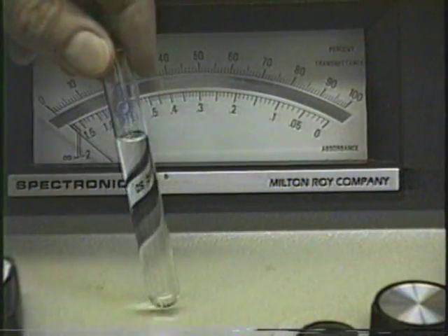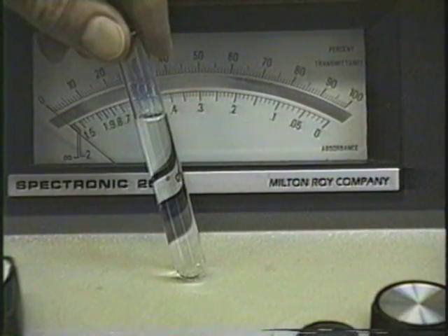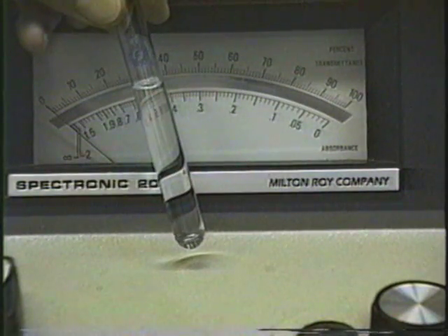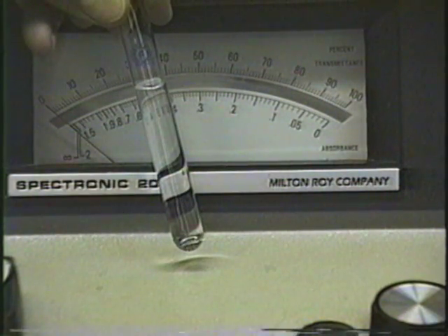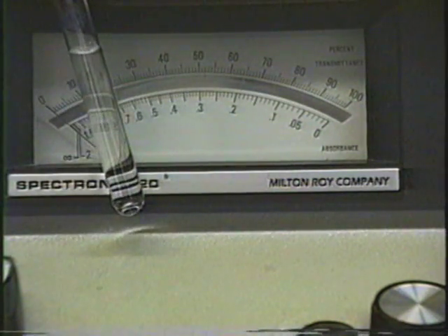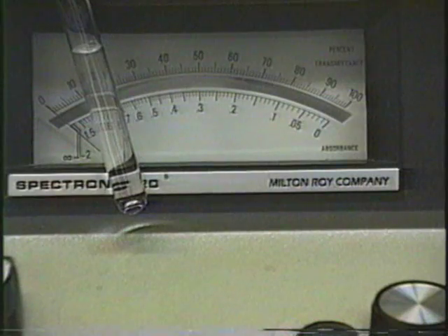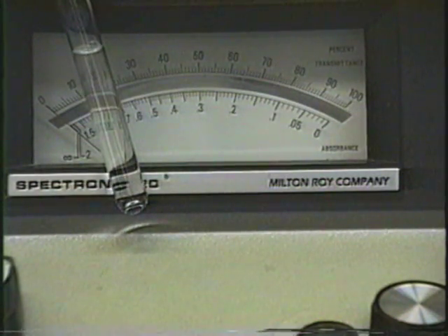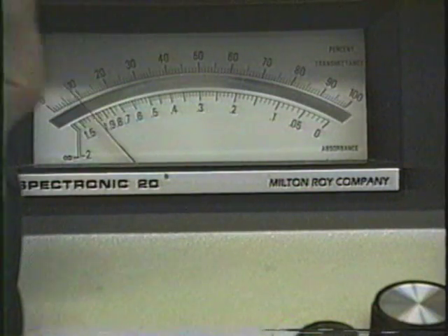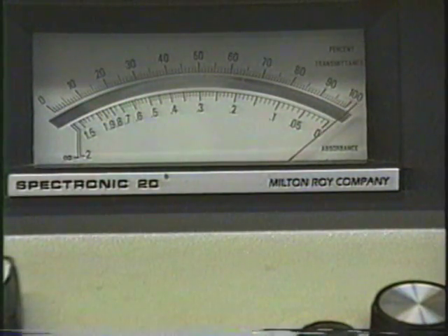Now we will put in our cuvette, the one that you're going to be using, not the reference. This is your regular cuvette. It's going to have nothing but distilled water. This is called the blank. We'll see what your cuvette reads with distilled water in. The machine's cuvette reads 100%. You use it to set the machine. Your cuvette may read something different. So let's put it in here and see what it reads.